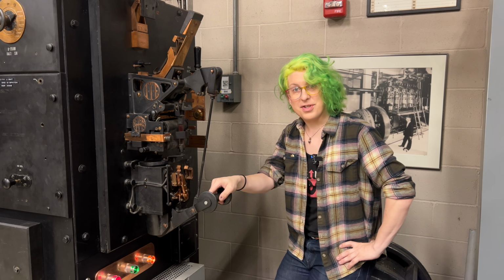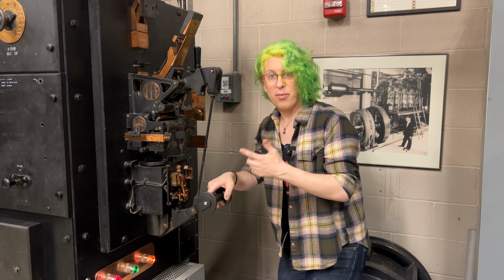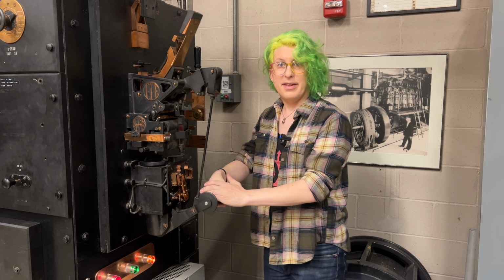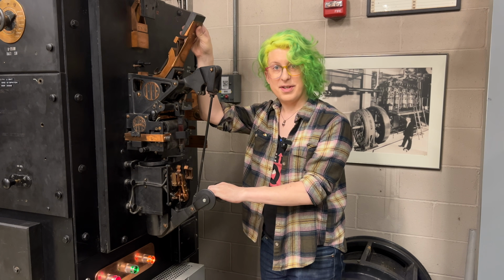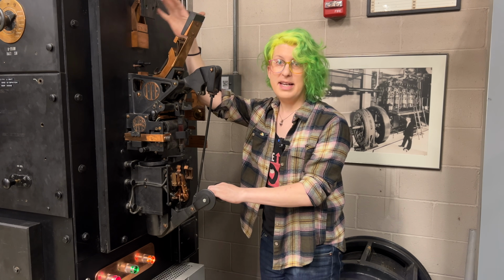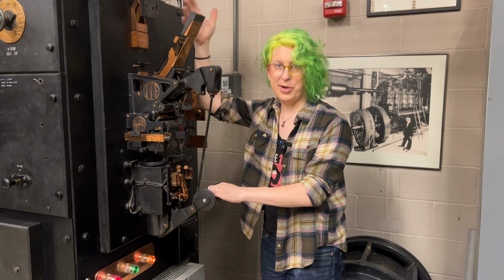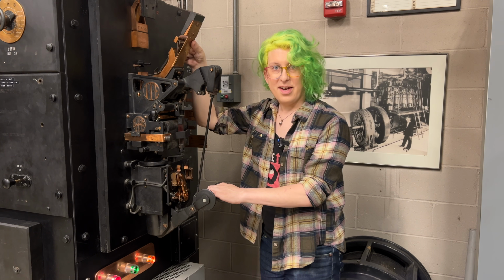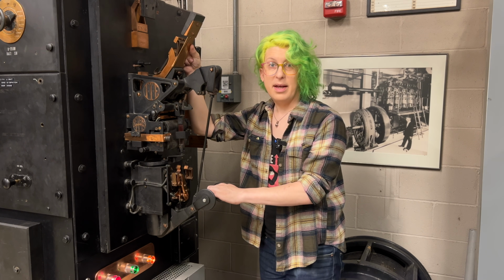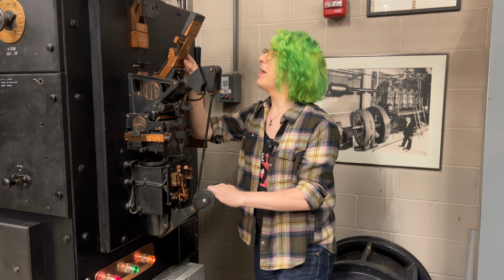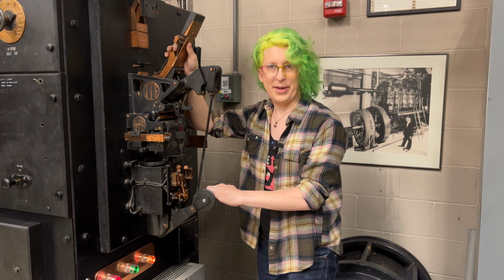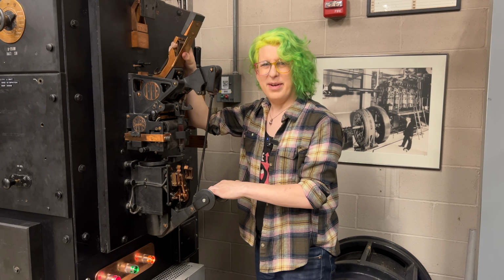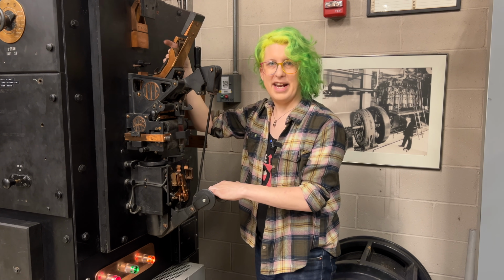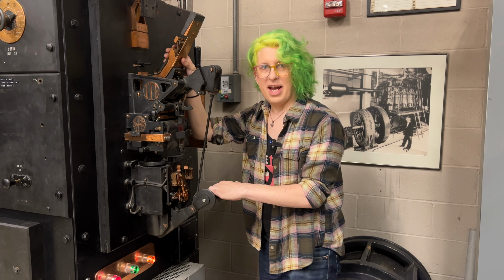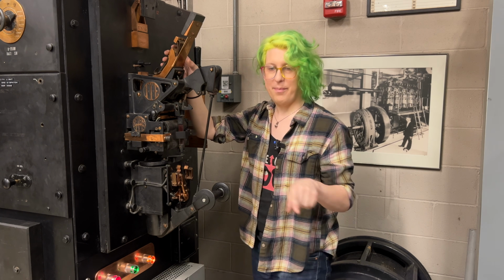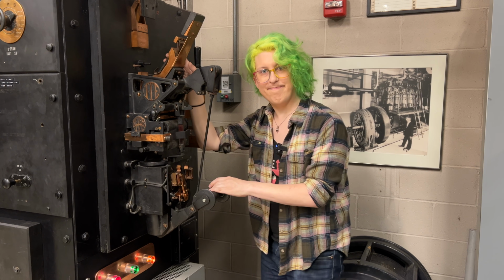This breaker features 3 make contacts. When the breaker is closed by this lever here, the top carbon contacts close first. These are sacrificial and can be easily swapped out just by unbolting them and putting on new ones. The second set of contacts are these right here. You can see the scarring and pitting from them opening and closing a bunch of times throughout their life. And finally, there's these laminated contacts at the bottom that make the connection last. These are what actually carry the significant portion of the current from the charging generators to the batteries.